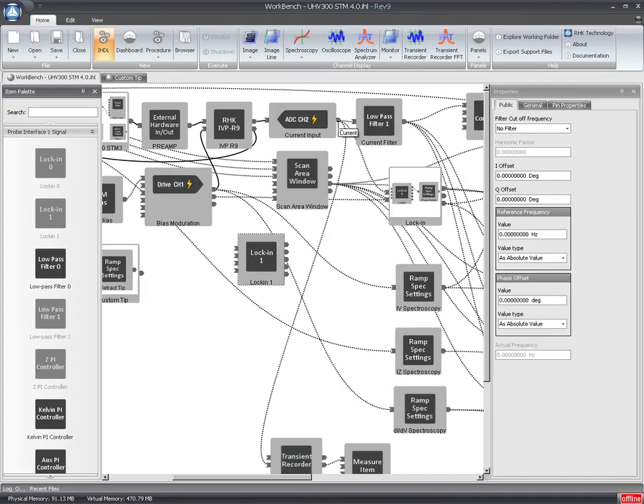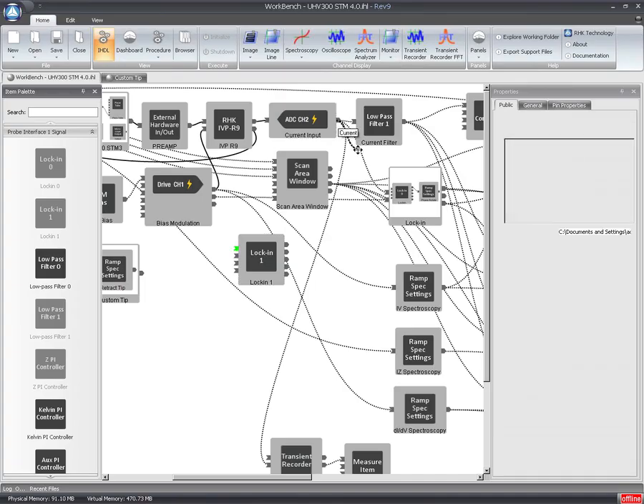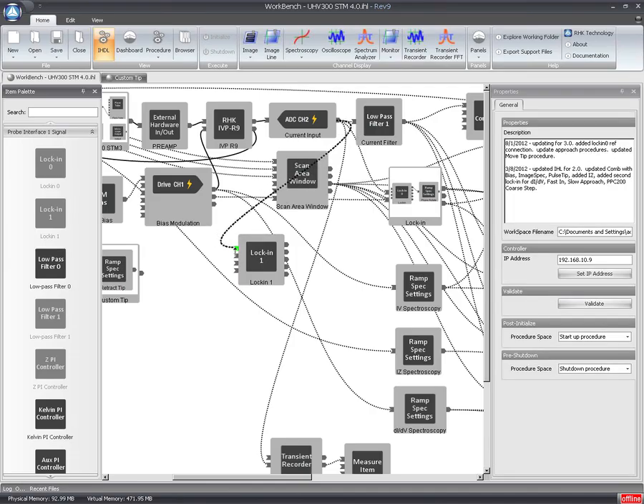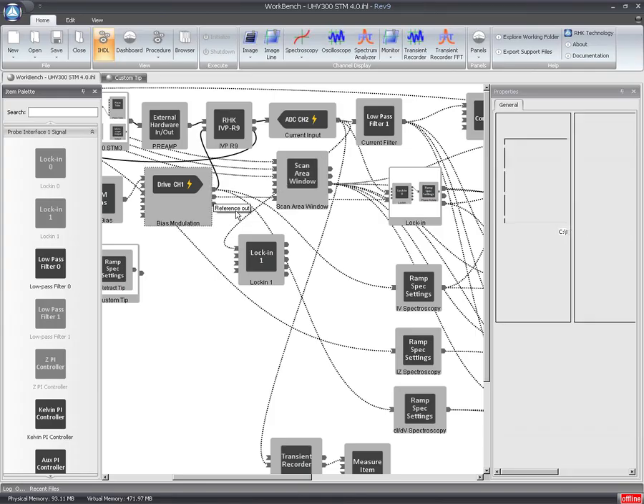Now I take the current signal from the A to D. As I drag, it'll show me this is where I connected to the lock-in. Now, if I want it referenced to the oscillator, the bias modulation, this is the bias modulation. This is its reference out. Now, you have to think of it a little differently because this is actually a digital reference out. Where a normal lock-in would be analog, here we can maintain zero noise and perfect precision.